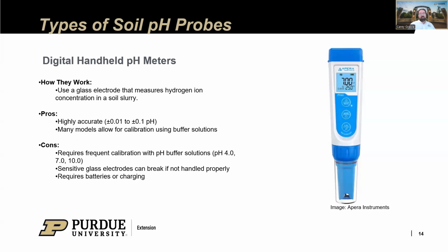There are various inexpensive solutions that you will have to purchase, and you run a calibration setting at various standards so that the machine can recalibrate itself. The electrodes can be broken if you don't handle them properly. They do need batteries, although on my own personal probe, I don't think I've changed the batteries since I bought it. So they do last a very long time.